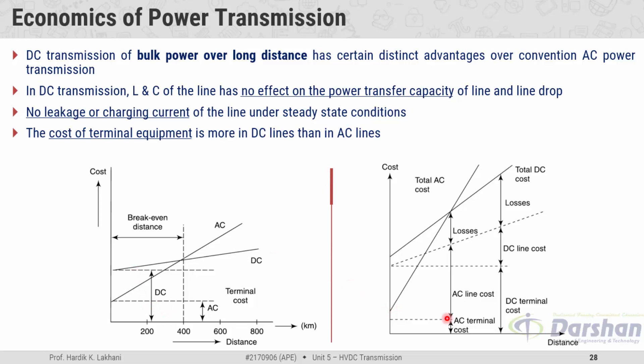In AC transmission, the AC terminal cost is less than the DC terminal cost. The line cost is more in AC compared to DC. The cost due to losses is much more in AC compared to DC for distances greater than the break-even distance. So the break-even distance is where the cost of AC and DC transmission systems becomes the same; beyond it DC is better, and below it AC is better.